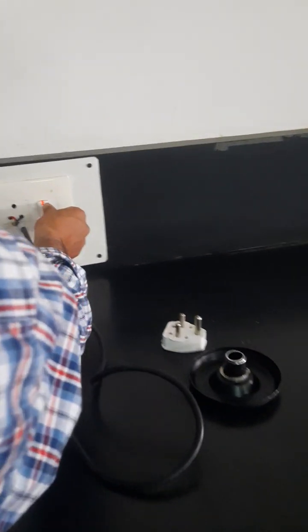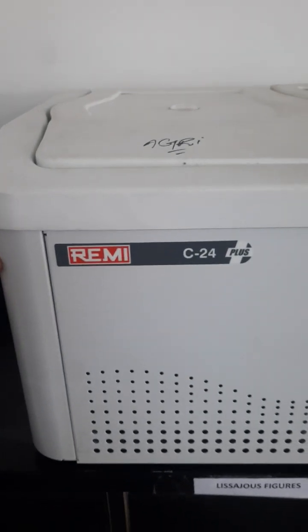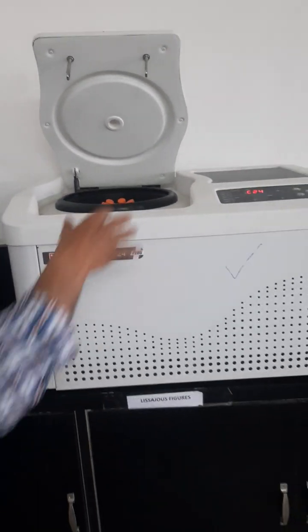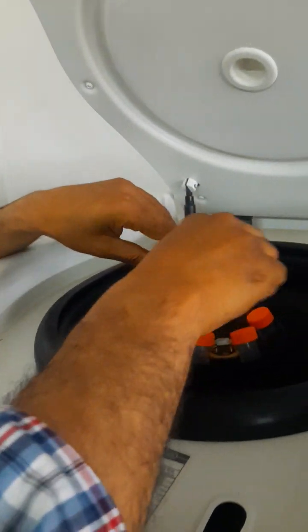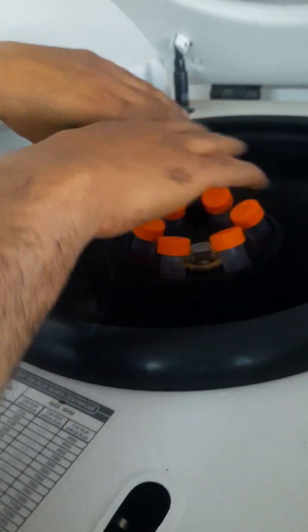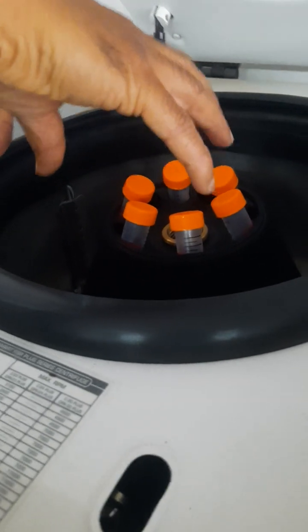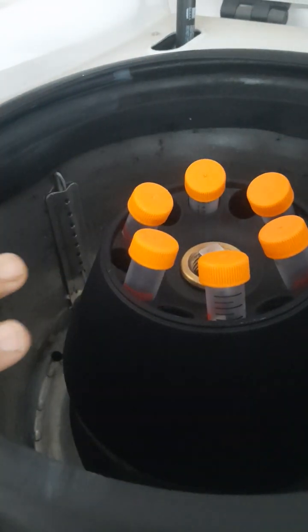I will put on the mains. This is the mains, I will check here. It is mains I have put on. Now I can open this lid by moving this latch. This is the opening of the lid. So this is the rotor. We have 15 ml centrifuge tubes here, and we have to insert these tubes in a manner that there is balance in this rotor. So we have set these tubes diagonally. This is diagonal to this, and these are opposite, so it has a balance. That is 3 this side and 3 this side. You can show it in a magnifying view that it has now 6 tubes, and we have set a balance here. So we can close this lid now.